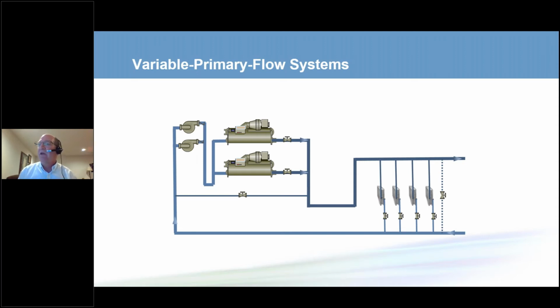Another thing you'll notice in the system is the bypass line has a control valve. And this control valve's purpose is when the system flow rate starts to drop below the chiller's minimum flow rate, that control valve modulates open so that we always keep the flow through the chillers above their minimum flow rate. That gives us good heat transfer. It gives us good, reliable chilled water leaving temperature control and good efficiency.